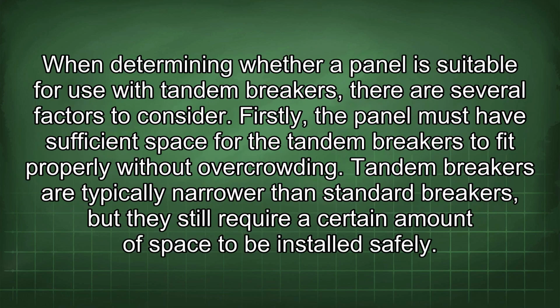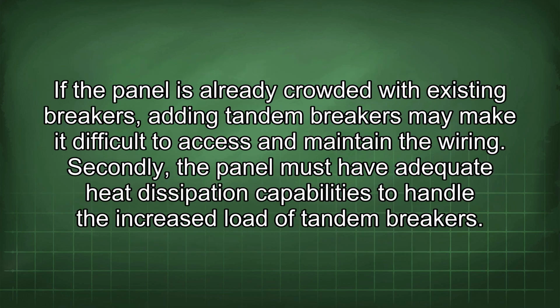When determining whether a panel is suitable for use with tandem breakers, there are several factors to consider. Firstly, the panel must have sufficient space for the tandem breakers to fit properly without overcrowding. Tandem breakers are typically narrower than standard breakers, but they still require a certain amount of space to be installed safely. If the panel is already crowded with existing breakers, adding tandem breakers may make it difficult to access and maintain the wiring. Secondly, the panel must have adequate heat dissipation capabilities to handle the increased load of tandem breakers.